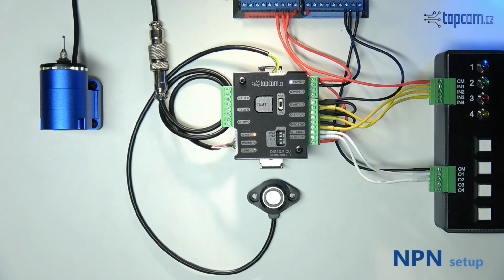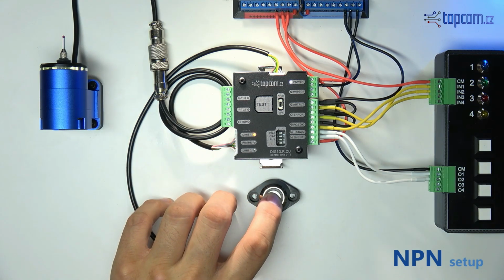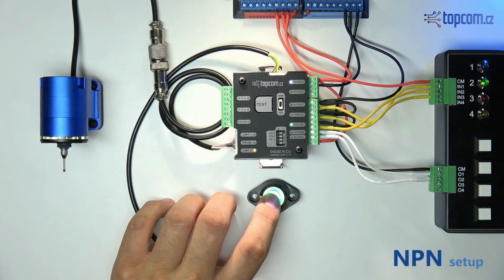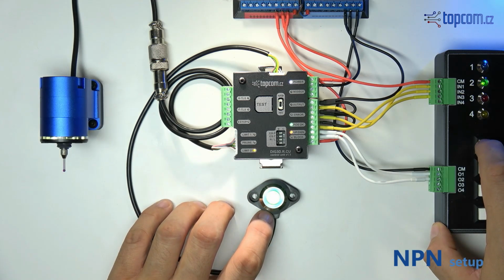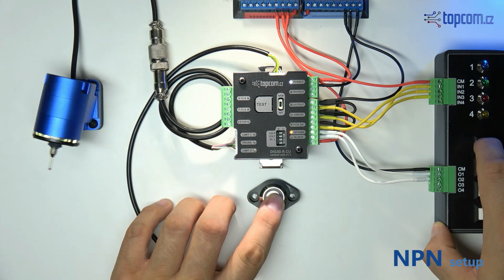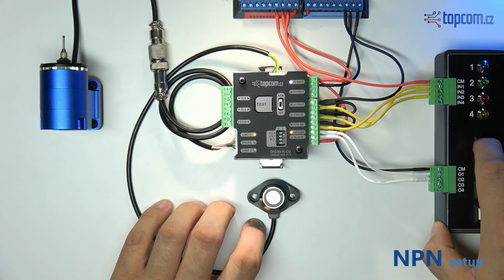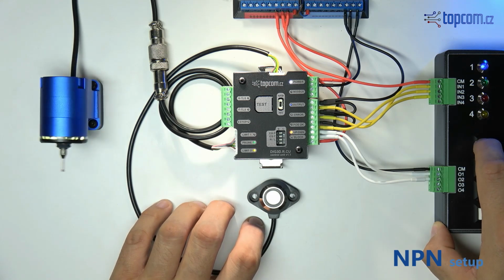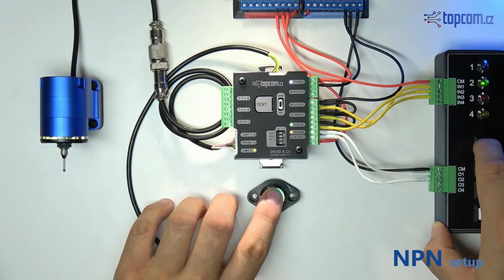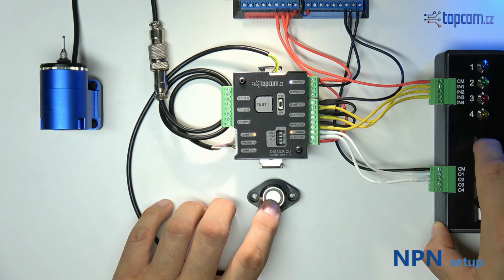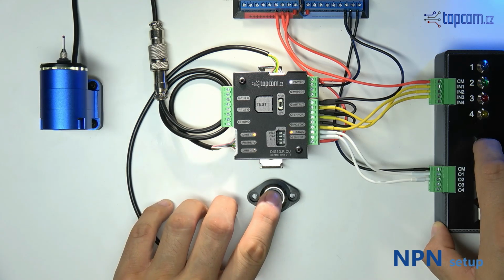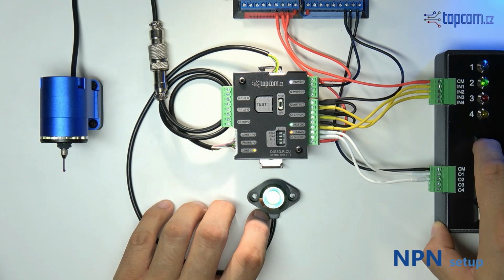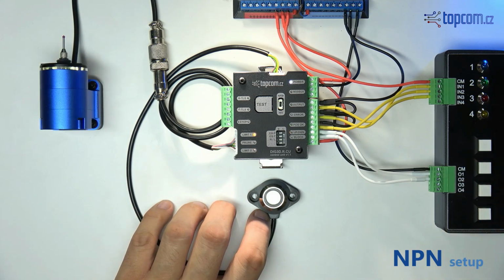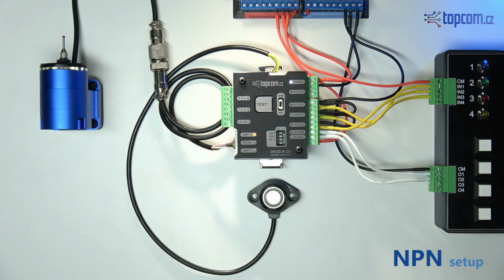The manual control button and the input from the motion control board can be used simultaneously. The button always operates in toggle mode and the control unit responds to the most recent change, whether from the button or the input. When the probe is in the working position, the position OK output remains active continuously. When the probe is in the home position, the signal is only active for a short moment and then stays inactive. This allows the motion control system to recognize whether the probe is ready for measurement.